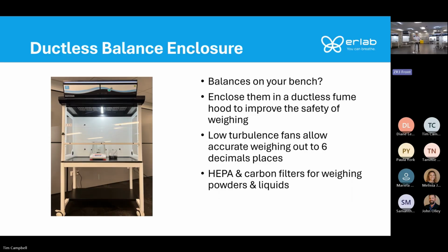And then the most common piece of equipment we see or recommend being put in our ductless fume hoods are balances. So think of our ductless fume hood as a ductless balance enclosure. If you look around your lab, you may see a balance on the open bench. A lot of times you see a balance on the open bench and they have access to a ducted fume hood, but it's too turbulent in the ducted fume hood. They can't get accurate weighing results. So they just have it on the open bench.